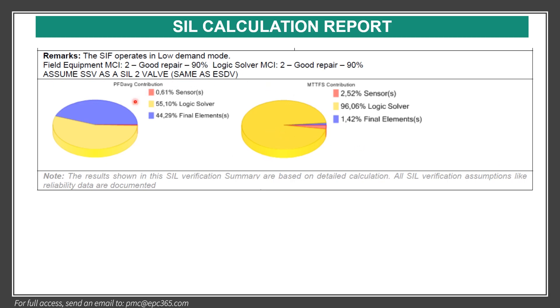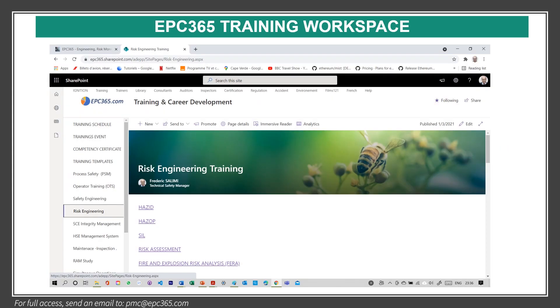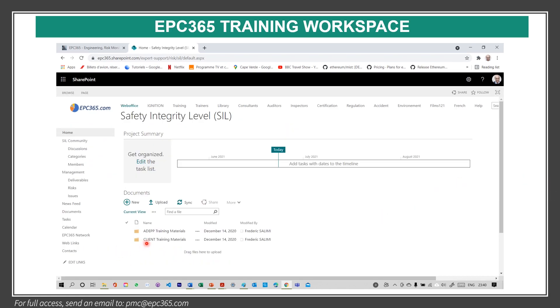The contribution chart shows that the sensor has very little contribution — mainly logic and final element in yellow. If we want to improve the system, we look at this and make a decision about improving the sensor, final element, etc. This e-course will be uploaded in the SIL risk engineering training workspace. For customized training, the company provides all the SIL information, and then we create an e-course for approval. When approved, it is posted for discussion.